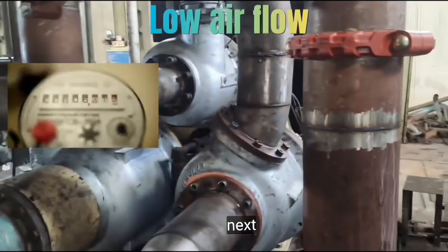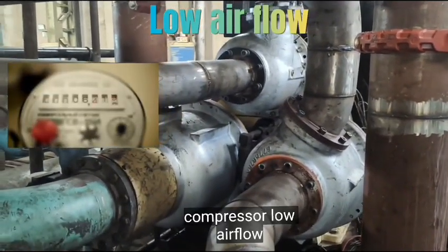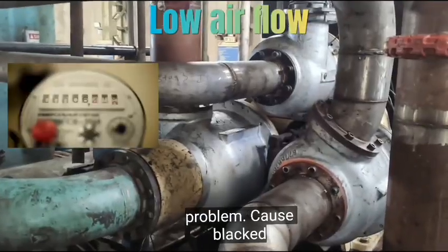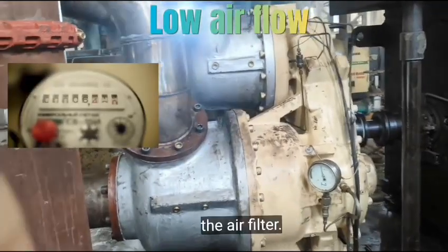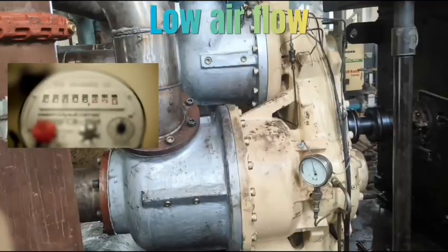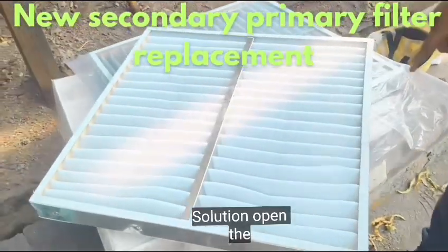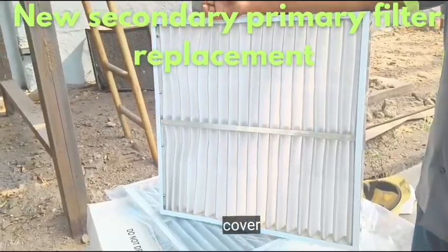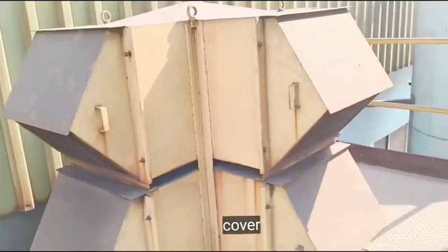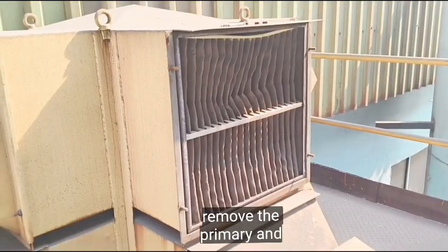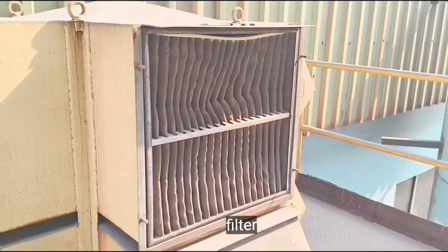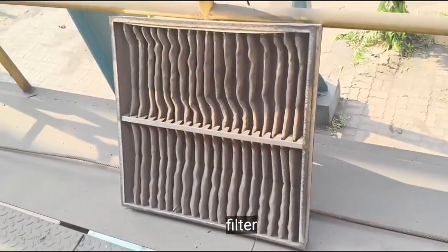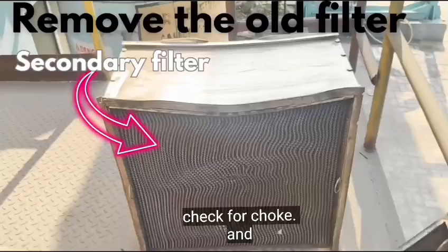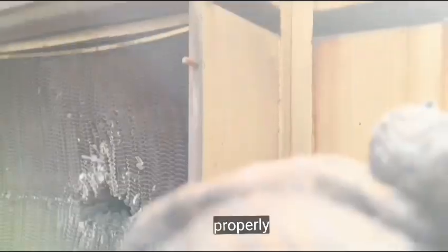Next, centrifugal compressor, low airflow problem. Cause: blocked air filter. Solution: open the filter cover. Remove the primary and secondary old filter. Check for soaking and clean properly.